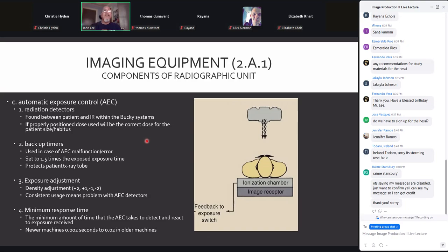Make sure that we set a backup timer just in case there's a malfunction. We want to set about 1.5 times the predicted exposure. It's hard to predict what mAs you would need for an individual based on their size measurement if you don't have good technique charts. So we're going to be kind of in the ballpark with these based on the technique charts that the digital system manufacturers give us. But remember, we want to be at that lower range of exposure whenever, just to stay within the confines of ALARA. Now, the other purpose of that backup timer, it does protect the patient, but it also protects our X-ray tube.